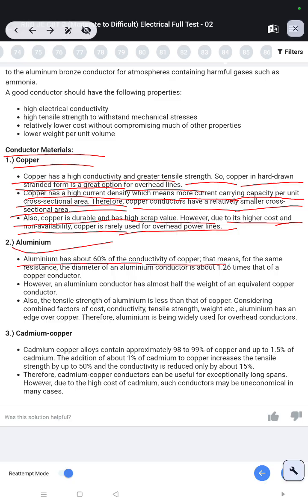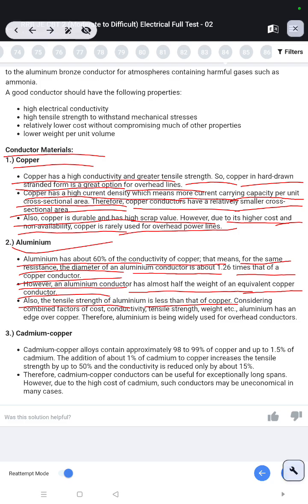That means for the same resistance, the diameter of an aluminum conductor is about 1.26 times that of a copper conductor. However, an aluminum conductor has almost half the weight of an equivalent copper conductor. Also, the tensile strength of aluminum is less than that of copper. Considering combined factors of cost, conductivity, tensile strength, weight, aluminum has an edge over copper. Therefore, aluminum is being widely used for overhead conductors.